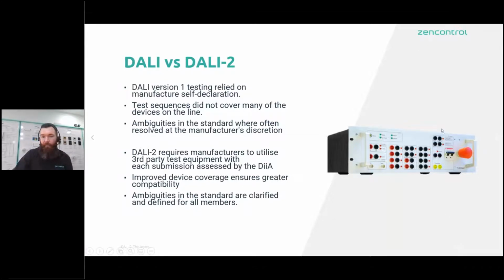Most commonly used is the Probit Lab, a 30,000 euro piece of equipment from a company in Germany. Once you've used that equipment, it generates test and certification files, and those files are sent to the DIIA where they are assessed. Someone actually checks that each test has been run correctly and that each result is valid, and that has to be approved before your device gets listed—for every variant of the device. So the scrutiny on devices listed as a DALI 2 product on the DIIA website is much higher.